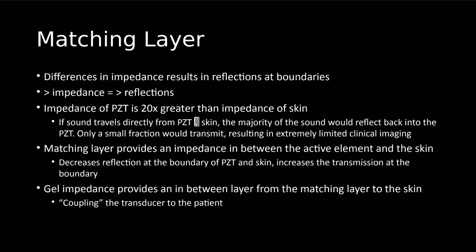So basically, when you put down that transducer without gel, the impedances are so great that it's going to produce this massive reflection, right? So it's not sending any sound waves into the body, because all the sound waves are being reflected right back into the transducer because the impedance difference is too high. So that wave can't travel into the body, right? It's almost like hitting a wall and saying, all right, I got to turn around and go home. So when you're putting that transducer on somebody without the gel, you are just getting that massive reflection back to you. Nothing is being transmitted into the body because of that.